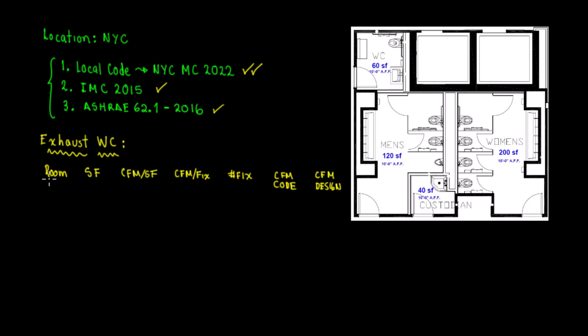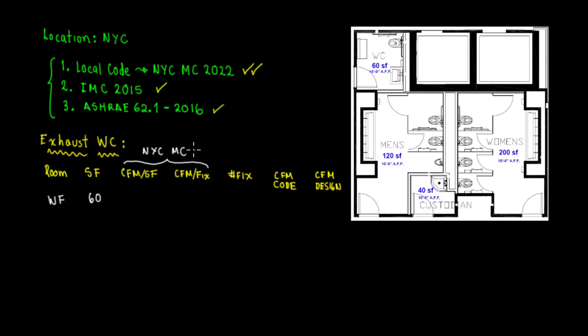The room is called WC. The square footage is 60 square feet. For the CFM per square feet and CFM per fixture columns, those values come from the code. We have three options: New York City Mechanical Code 2022, IMC 2015, or ASHRAE 62.1-2016. In this case we're going to use the NYC New York City Mechanical Code 2022. We need to go to the code tables to get this information.